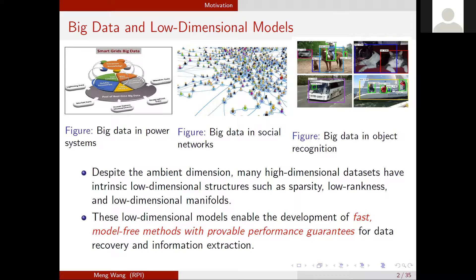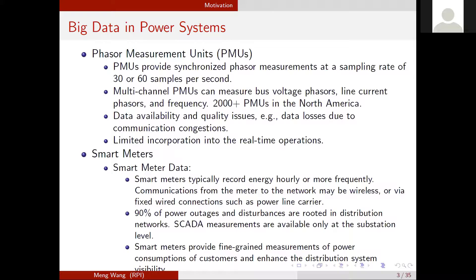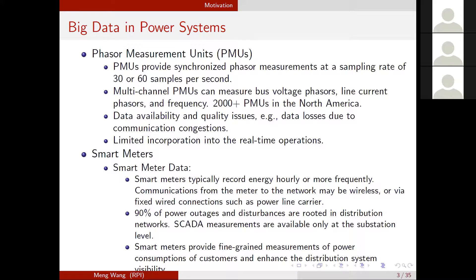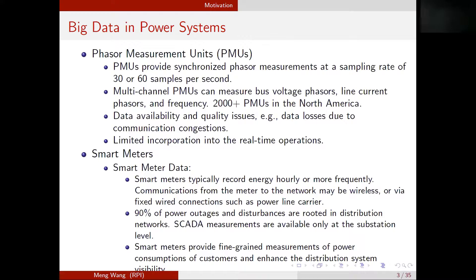We are going to focus mostly on power system applications. The data we will focus on is real-time PMU data. Nowadays, we have more than 2,000 PMUs installed in North America. The sampling rate is about 30 or 60 samples per second, and there are usually multi-channel PMUs that measure voltage phasors, line current phasors, and frequency. There are data quality issues: operators observe data losses and sometimes data errors due to device issues, scaling problems, or communication congestion. Due to these issues, PMU data is not yet incorporated into real-time control operations.